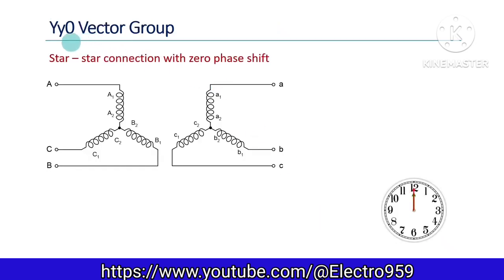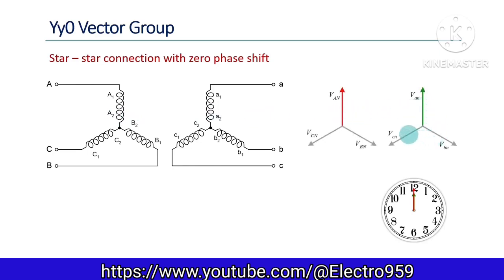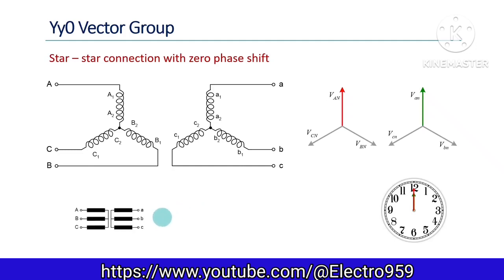The first type we are going to discuss is the YY0 vector group. It has a star-star connection, meaning both primary and secondary windings are star connected. In the phasor diagram, the three voltage phasors are 120 degrees apart. The secondary winding voltages in all three phases are in phase with the corresponding primary voltages. The phasor positions of one phase are represented by clock hand positions, with the red hand representing the primary phasor and the green hand representing the secondary phasor. Here the phase difference is zero, corresponding to the zero o'clock position — that is how this vector group is named YY0.